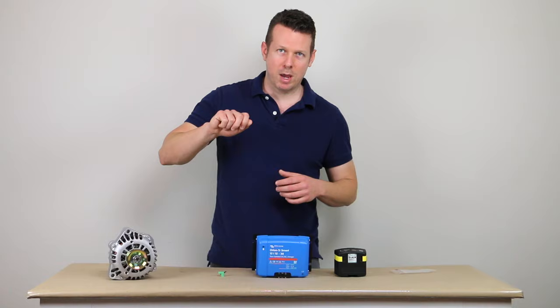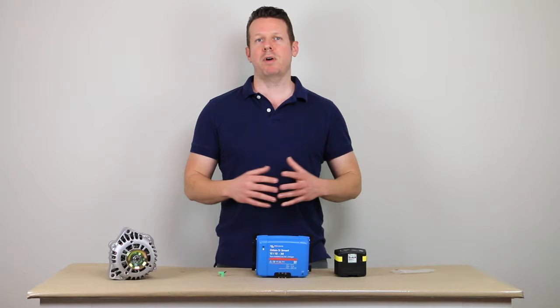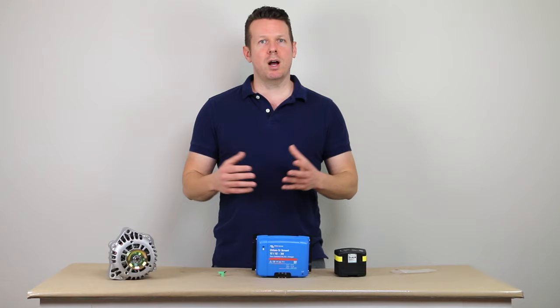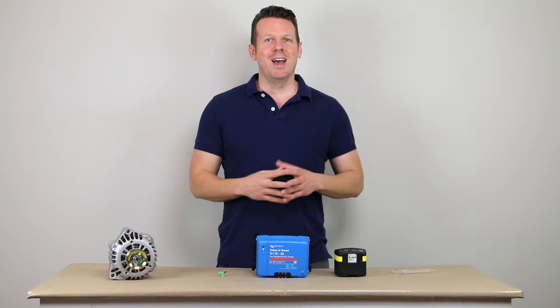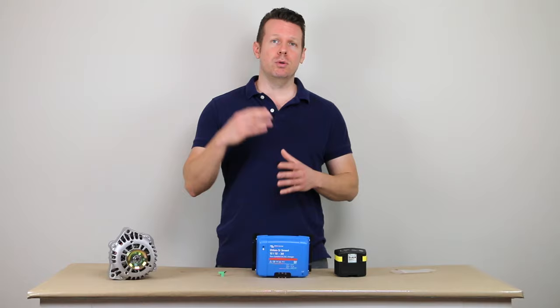Loose connections are going to get hot and they could melt things or cause a fire. And so in general, you want to make sure that connections didn't loosen overnight, especially because we have vibration and things will shake loose out of there. And then oftentimes I hate to say it, but we're assembling these electrical systems and somebody is over there talking to us. And we forget to tighten a bolt.